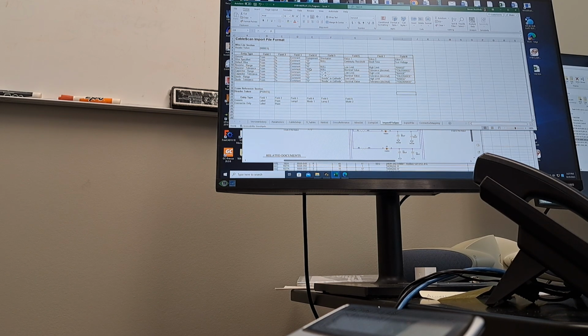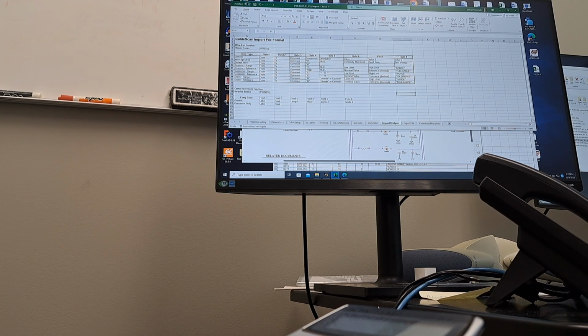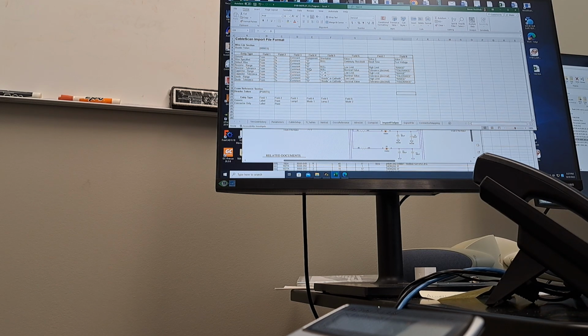Whereas if we do it by using the merge wires, it's going to say that J11 to J21 is open. And it's not going to know anything about F1 or any of that stuff. So that's the thing to keep in mind as you're doing the program. All right. Any questions about this stuff so far?